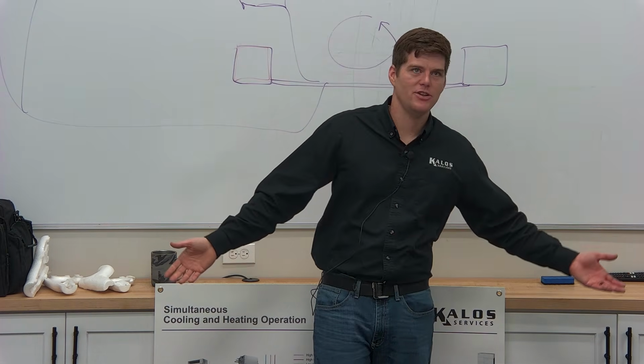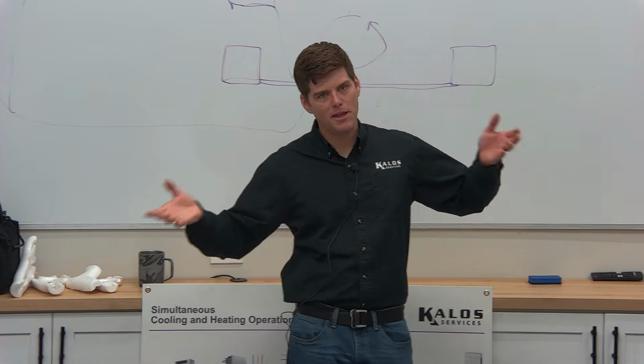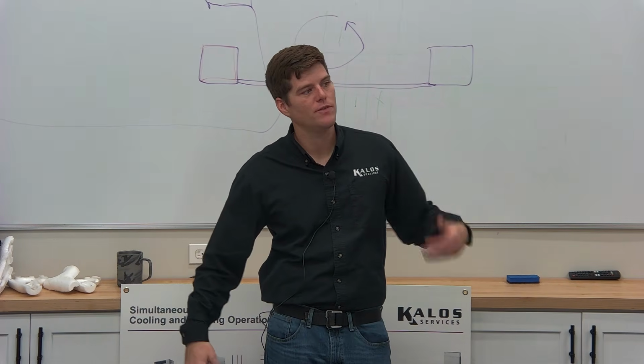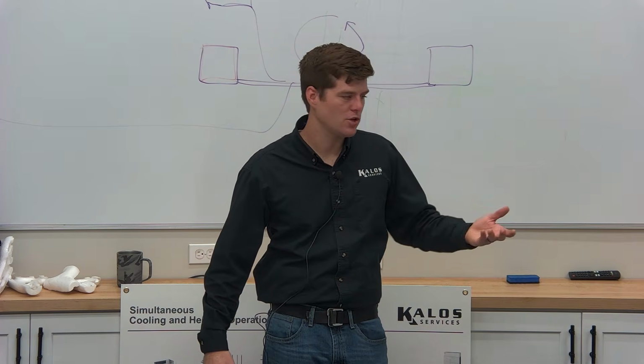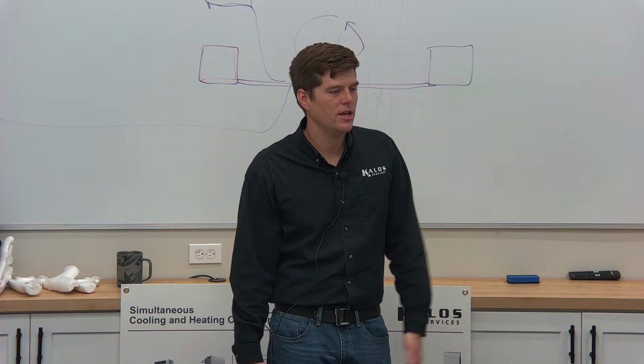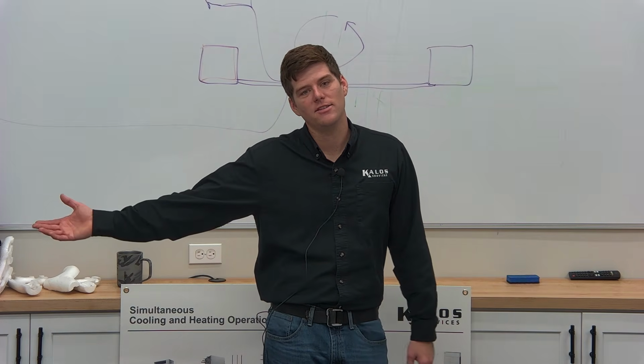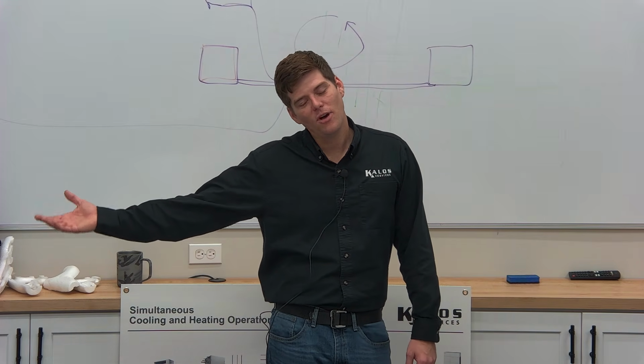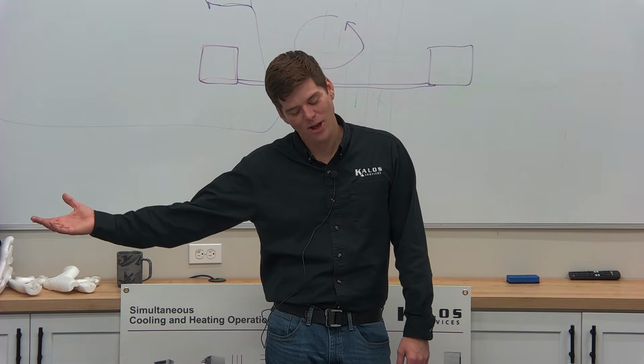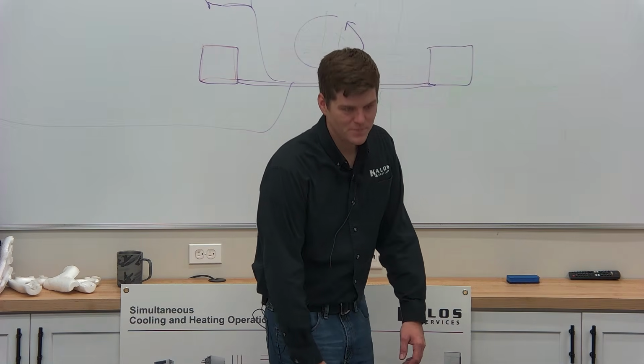Now, there are certain limitations with anything else. Most manufacturers have an outdoor ambient lockout, so if it's above 75 degrees, it won't let a box go into heating. It won't let an indoor unit go into heating. The unit is smart enough to look at outside and say, really? You want heat? Come on. No, I'm not doing that. That's stupid. What causes the limit?